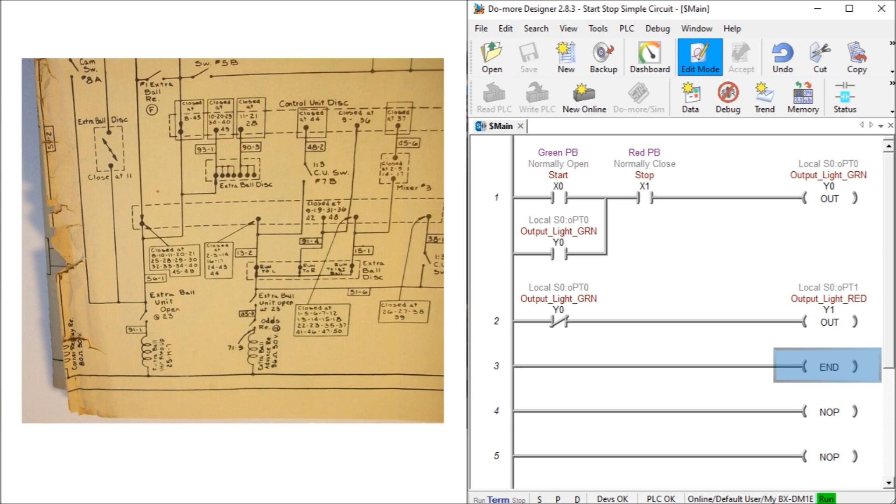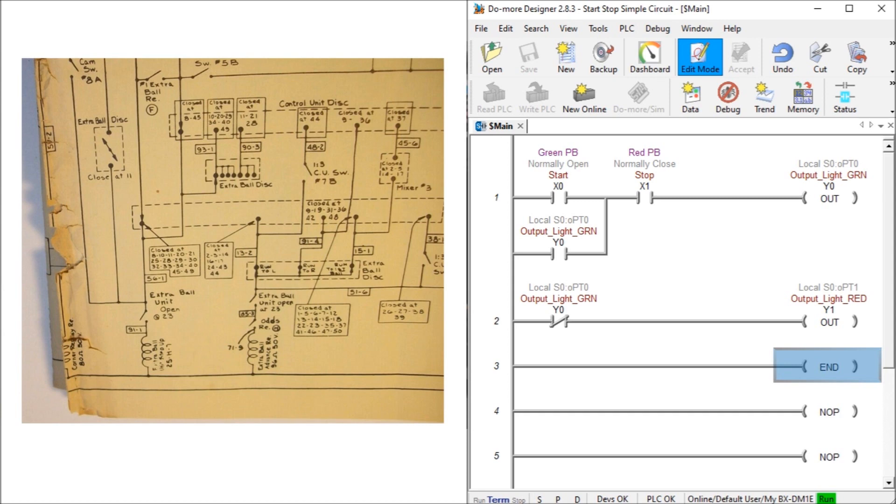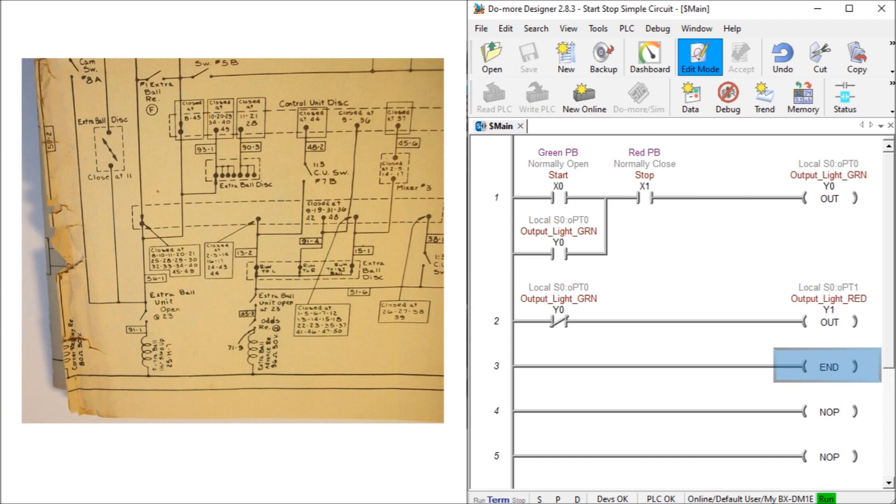Now reading the ladder logic in the PLC. The PLC ladder logic is read from left to right, top to bottom. So just like our reading, the ladder logic is solved. And the output or logic from the previous rung is available to the next rung to use. Outputs in the logic are located on the right hand side of the ladder logic. And the inputs are usually associated on the left hand side.